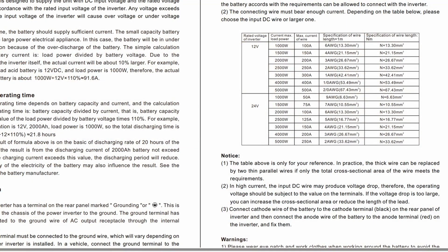Earlier I had mentioned that I thought I could get away with some smaller wire size connecting the two battery banks together and I want to explain that here just a little bit. If we look at the manual that was provided by the inverter manufacturer, they've got a table in the manual that shows the recommended wire size gauges.